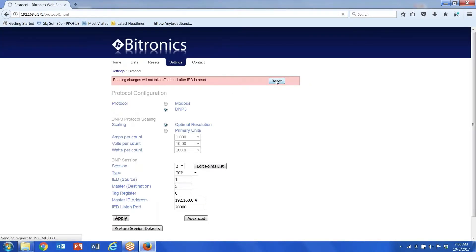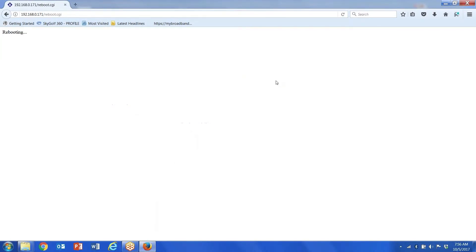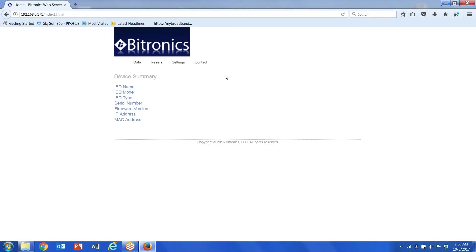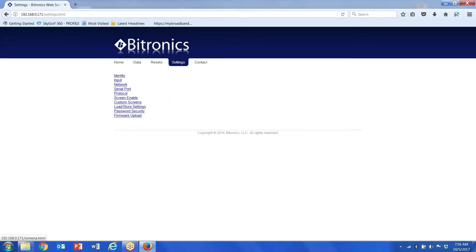For your particular application, you want to go to a 16-bit counter, so we make the change there and click Apply. It's going to ask you to reset — click Reset. Within a couple of seconds the meter will go through a reboot process, come back online, and the changes should have taken effect. If not, don't hesitate to call or email, and we can always do a live GoTo Meeting session as well.